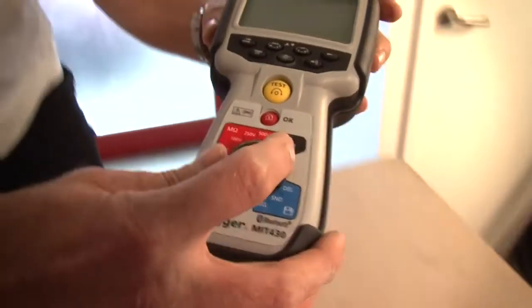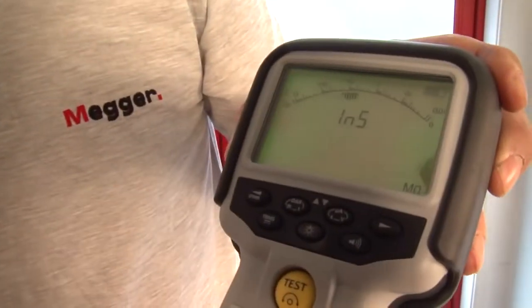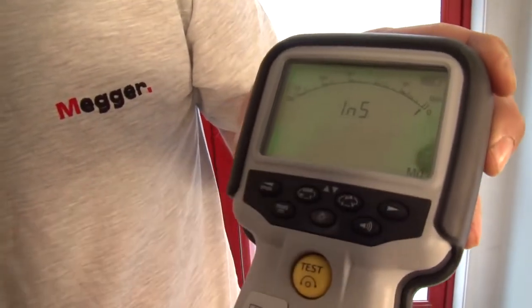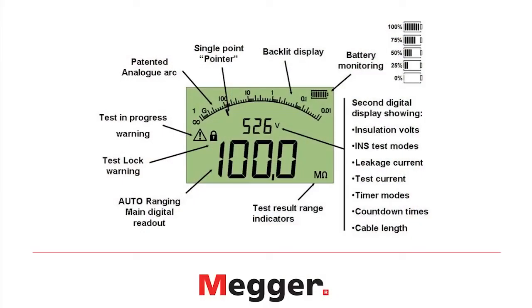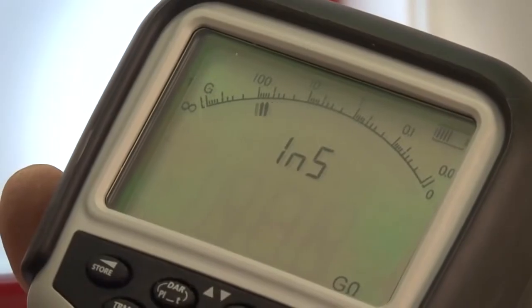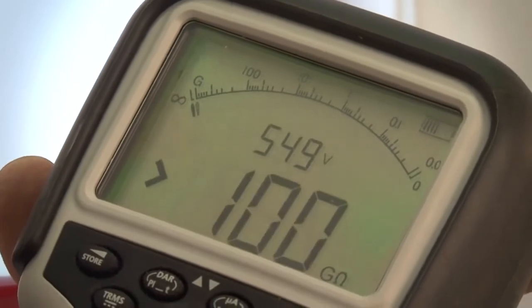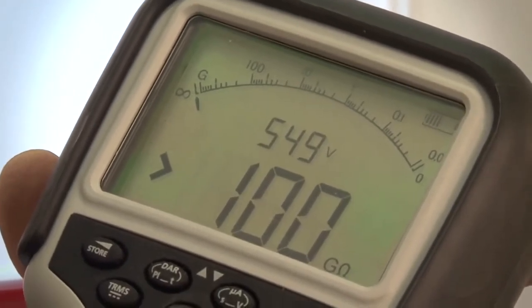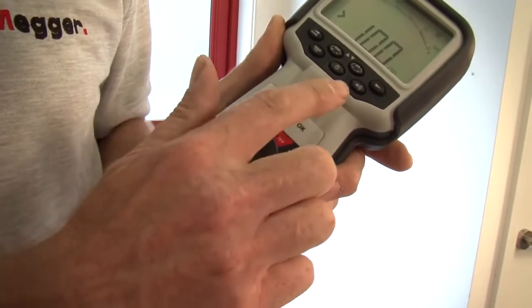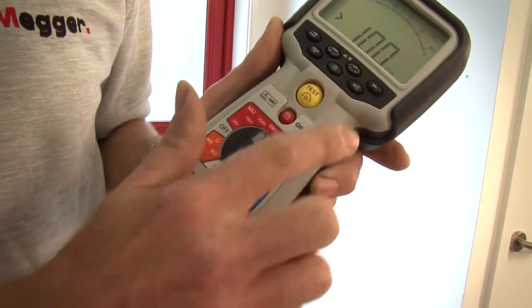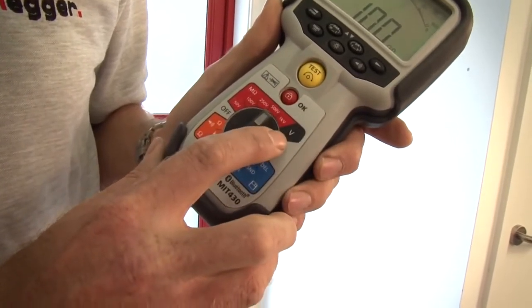Now, all instruments have a dual display analog arc LCD that is backlit. The dual display enables you to see the value of the insulation resistance and at the same time the actual test voltage which is being applied. The analog arc enables you to see things like capacitive charging currents or varying readings. The products will also measure continuity, and they have a selectable continuity buzzer. And they'll measure voltage, AC and DC, true RMS.